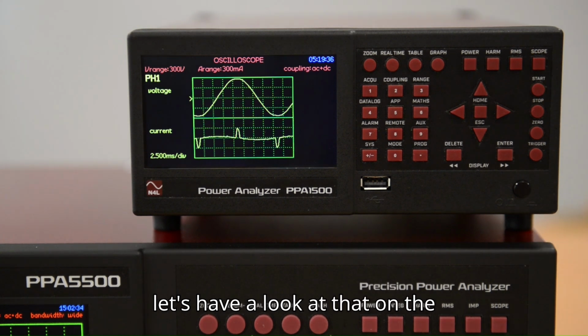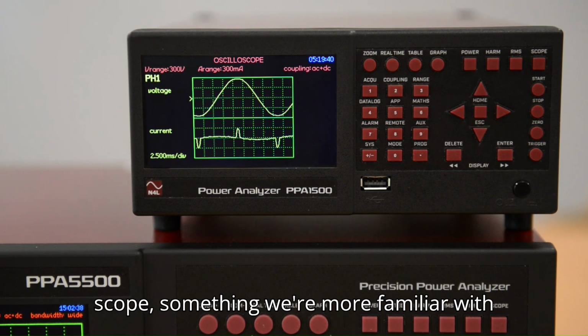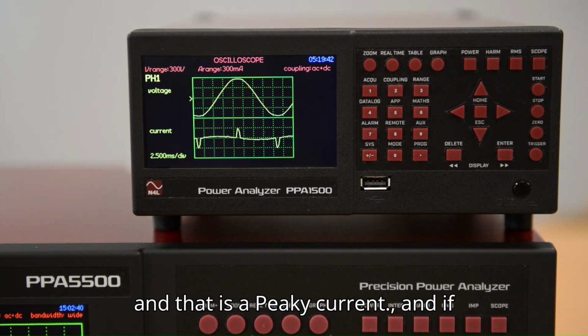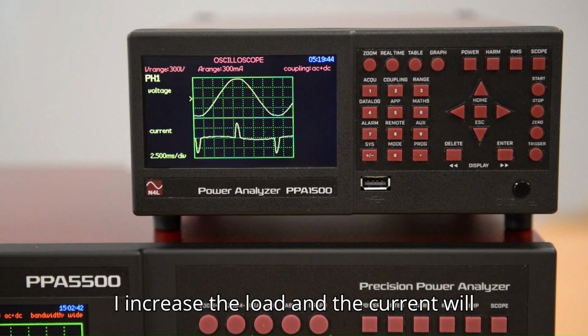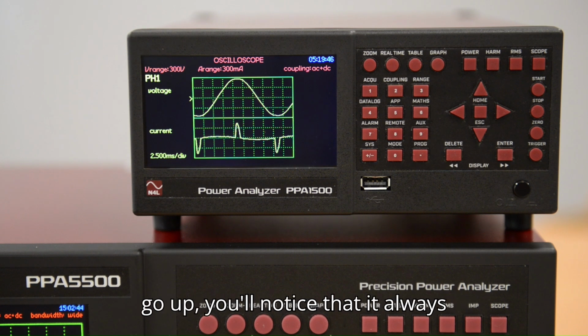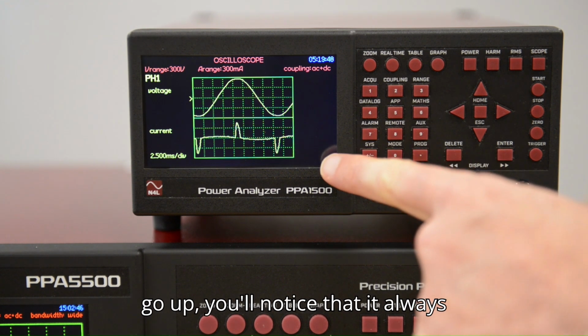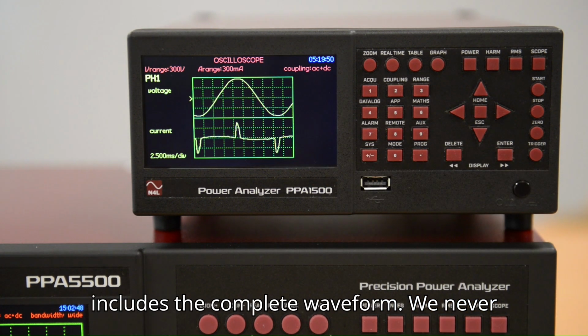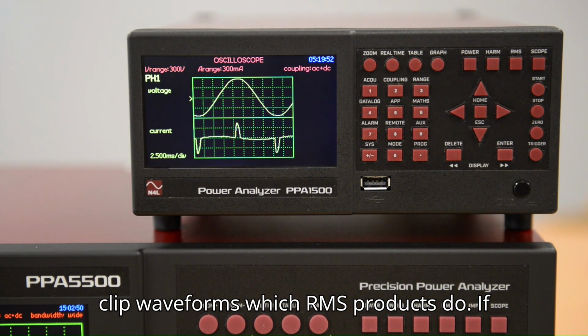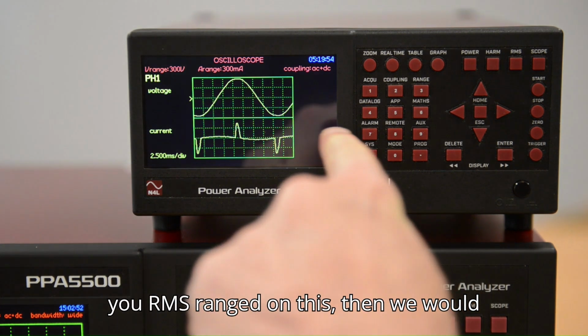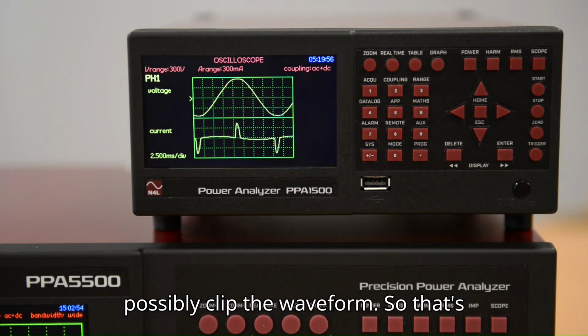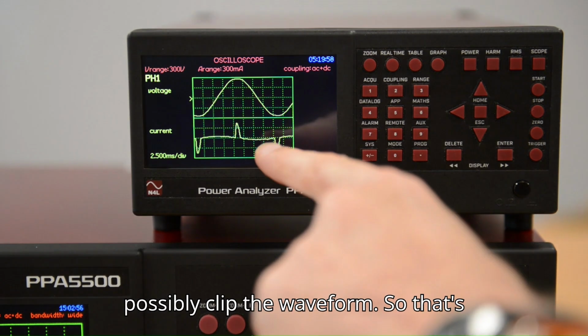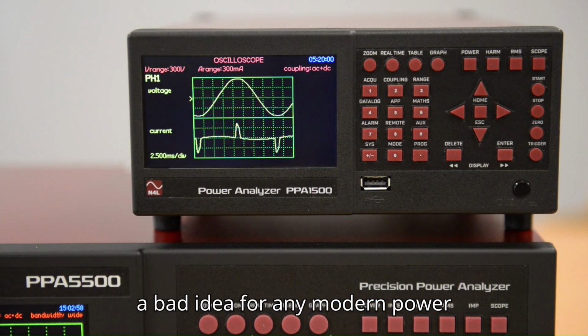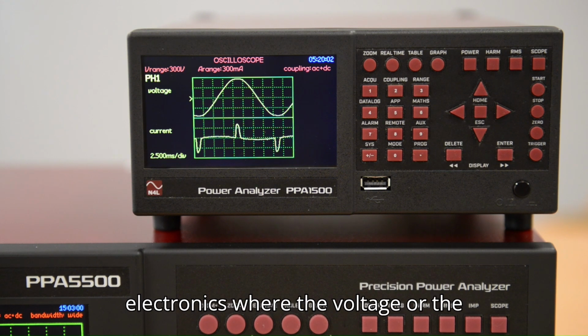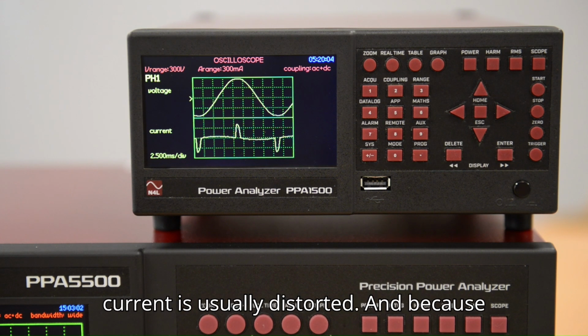But let's have a look at that on the scope. We're seeing what we're familiar with, and that is a peaky current, and if I increase the load, then the current will go up. You'll notice that it always includes a complete waveform. We never clip waveform, which RMS products do. If you're RMS ranged on this, then we would possibly clip the waveform. So that's a bad idea for any modern power electronics, where the voltage or the current is usually distorted.